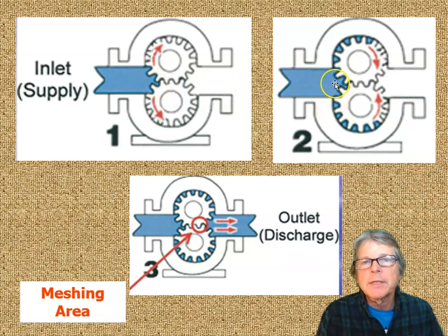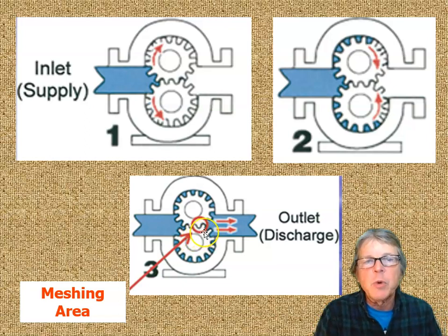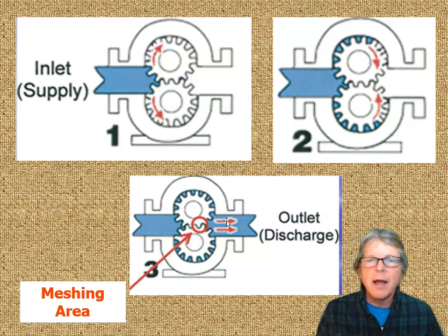In number two, we can see fluid going around the teeth, around the outside. Then as it gets to the discharge area, number three shows the meshing area where the teeth mesh together. Where the teeth mesh together, it squeezes the oil out. There is only one way this oil can go, and it's out the outlet. It can't go back because there's more oil coming towards it. It's like trying to walk backwards at the end of a baseball game when the whole crowd is going out to the parking lot. This meshing area squeezes the oil out, doesn't let it go through the center, and forces it out to discharge.